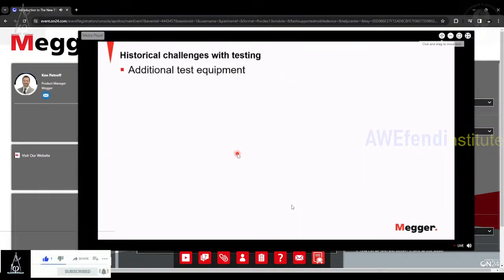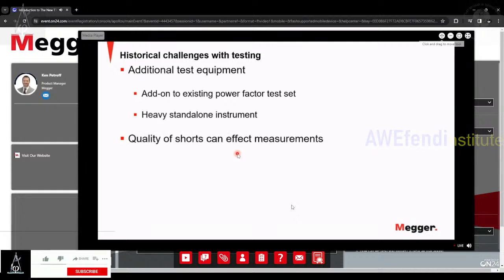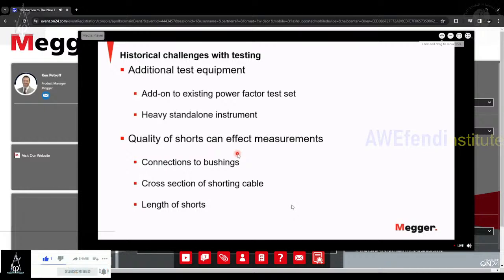So some of the historical challenges: this has typically required a dedicated, high current power test set. Sometimes it was an add-on to an existing power factor test set, or it was this heavy standalone instrument. And since the quality of the shorts could affect the measurements, the connections to bushings could always be questionable, and it wasn't really seen as a routine test that a lot of people wanted to perform because it was extremely difficult to get repeatable, reliable results.